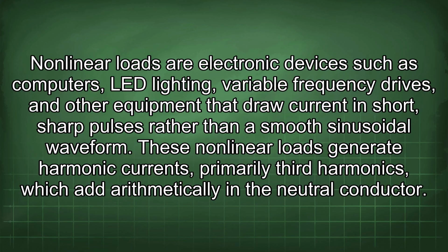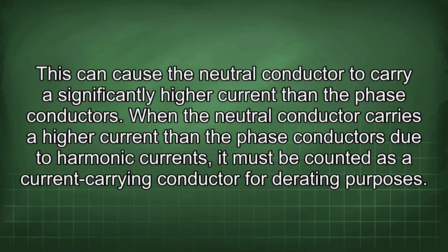Nonlinear loads are electronic devices such as computers, LED lighting, variable frequency drives, and other equipment that draw current in short, sharp pulses rather than a smooth sinusoidal waveform. These nonlinear loads generate harmonic currents, primarily third harmonics, which add arithmetically in the neutral conductor. This can cause the neutral conductor to carry a significantly higher current than the phase conductors.